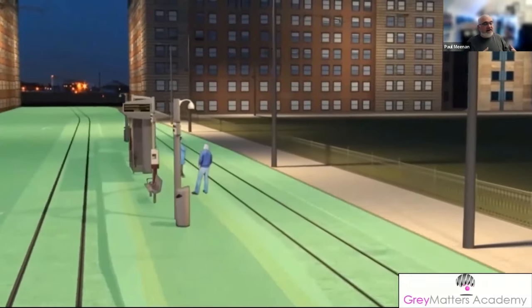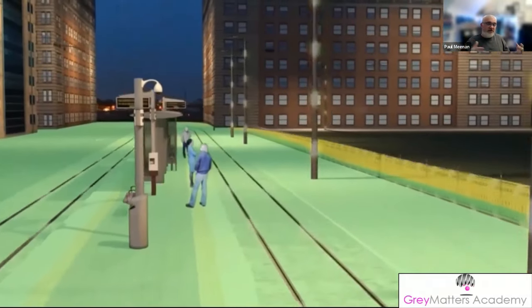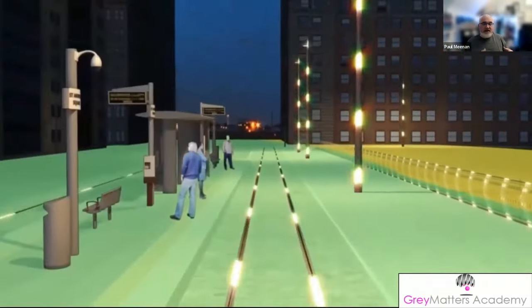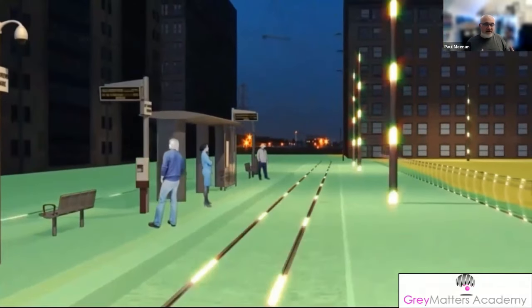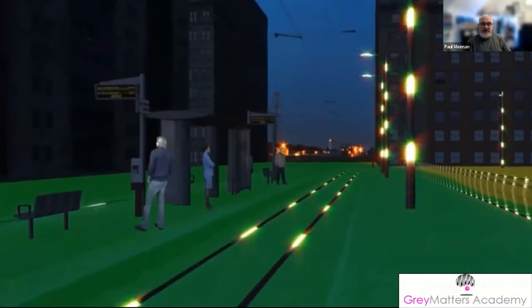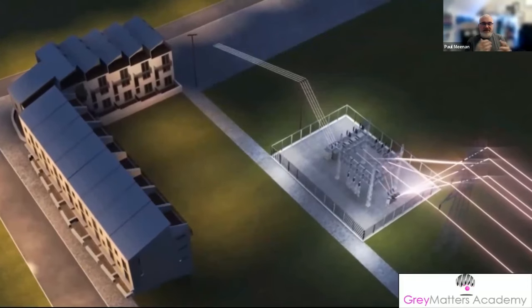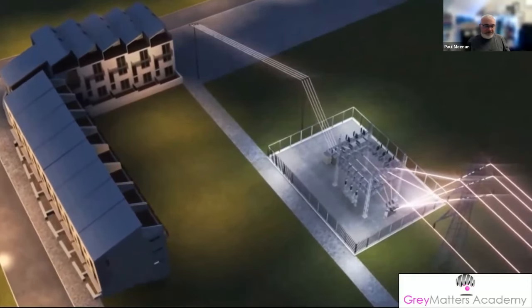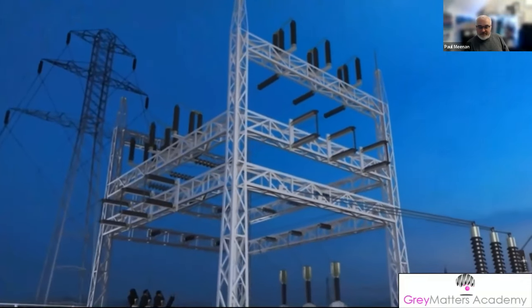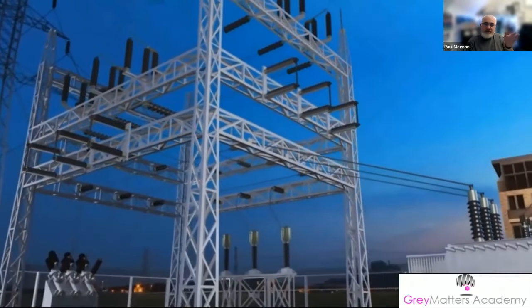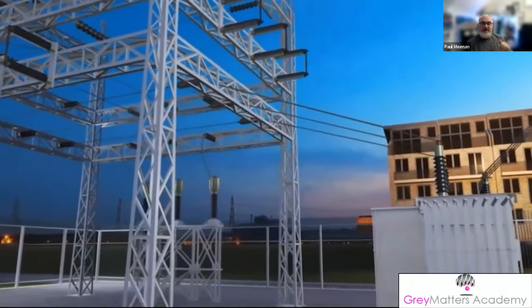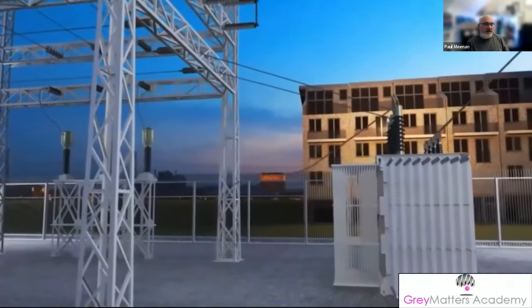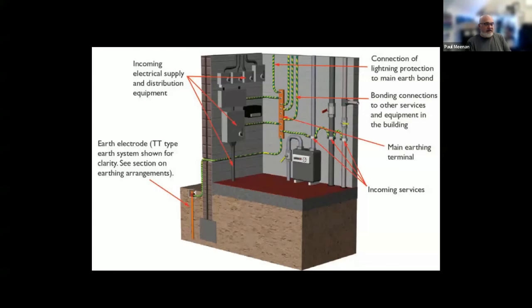As you can see, as that gradient dissipates and the voltage lowers the further it goes, it can energize and appear on exposed or extraneous metalwork and circuits. And electricity has a tendency to go where it wants and do what it wants. We have a requirement to control and manage and configure that electrical installation as best as we can. So how do we do it? Well, we basically bond everything together with a bit of green and yellow cable.